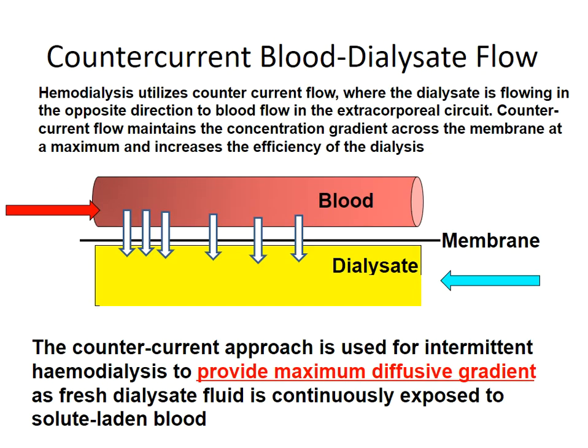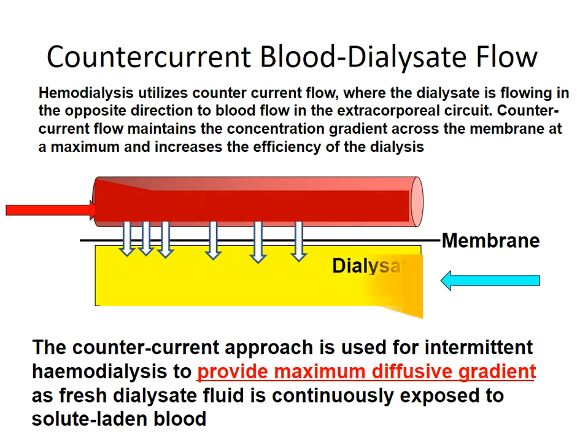The counter-current blood dialysate flow means that the dialysate is flowing in the opposite direction to the blood flow in the extracorporeal circuit. Counter-current flow maintains the concentration gradient across the membrane at a maximum and increases the efficiency of dialysis. The counter-current approach is used for intermittent hemodialysis to provide maximum diffusive gradients and maximum removal of uremic toxins, as fresh dialysate fluid is continuously exposed to solute uremic toxins-laden blood.